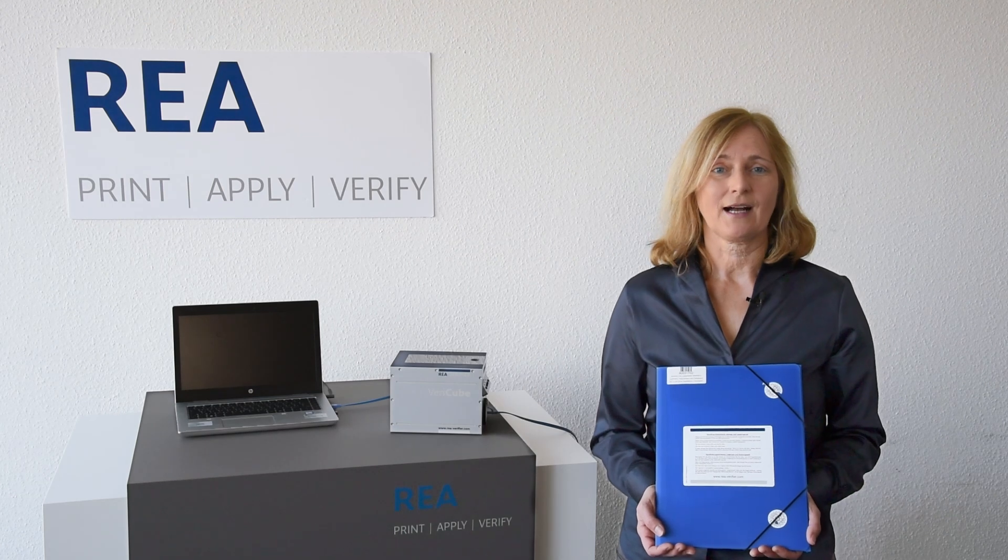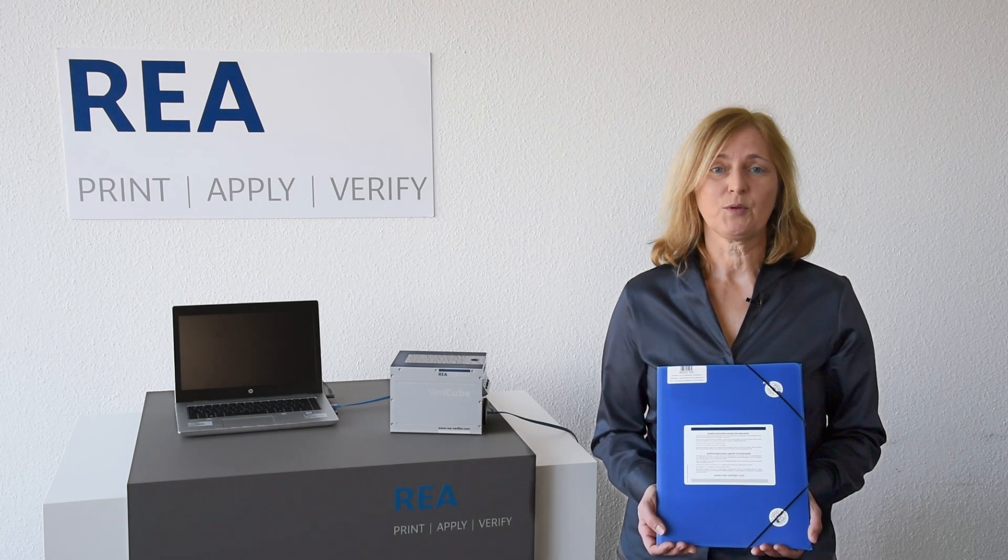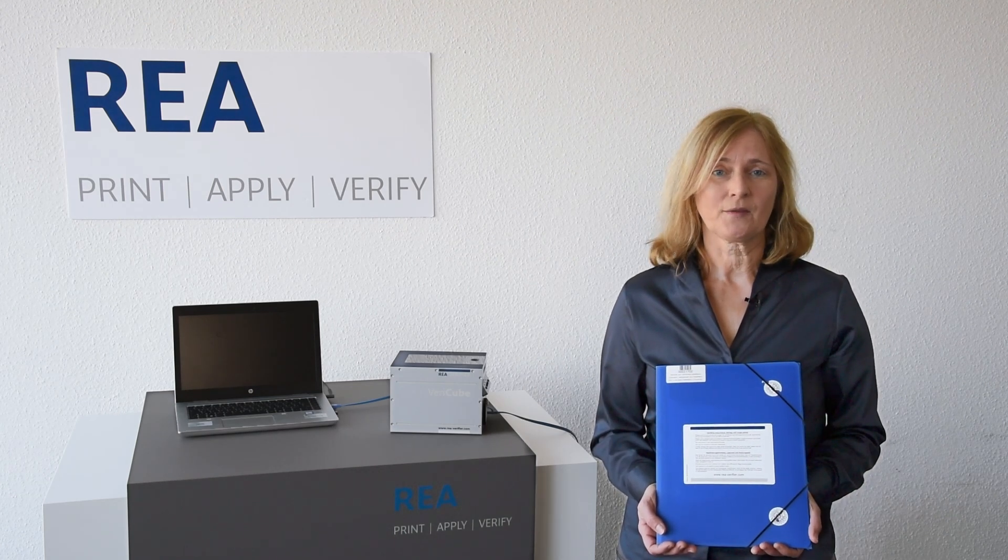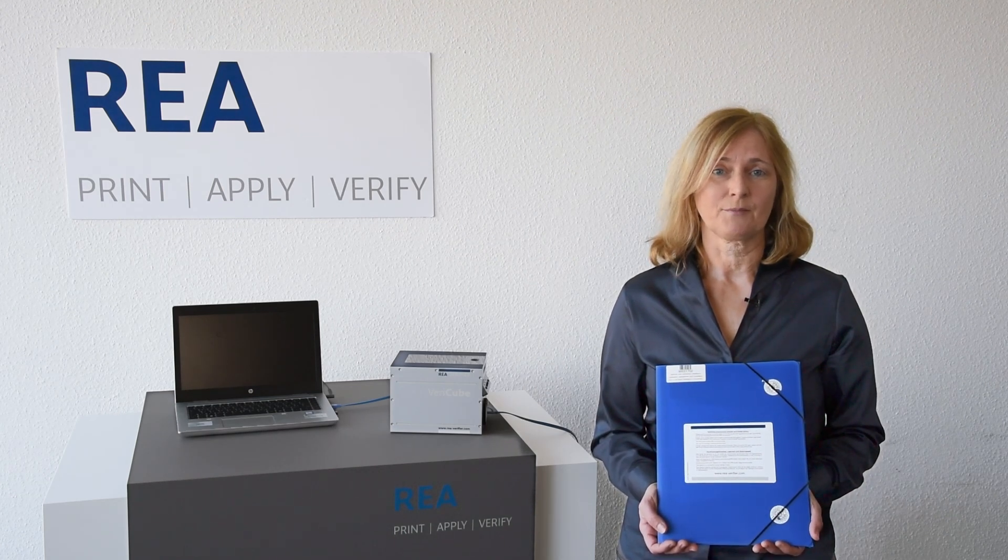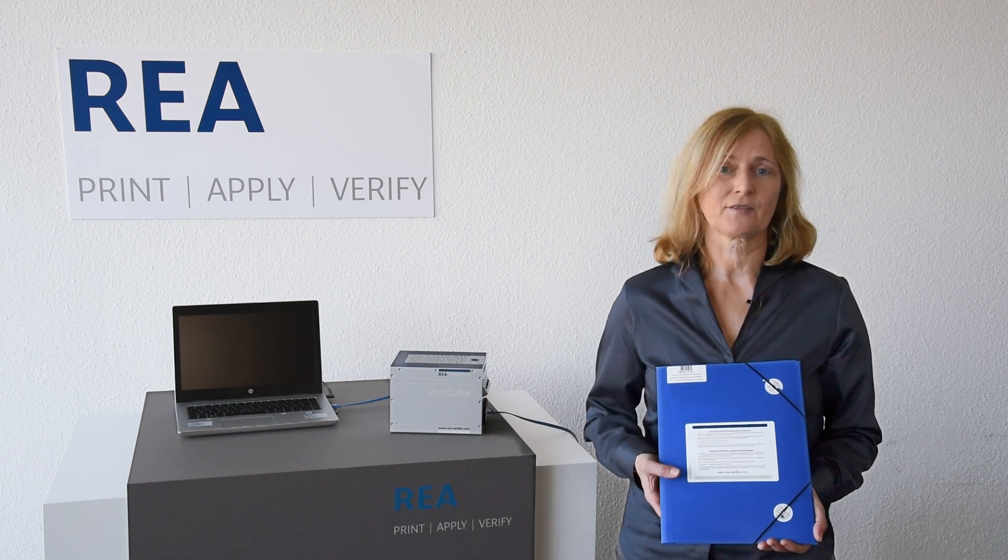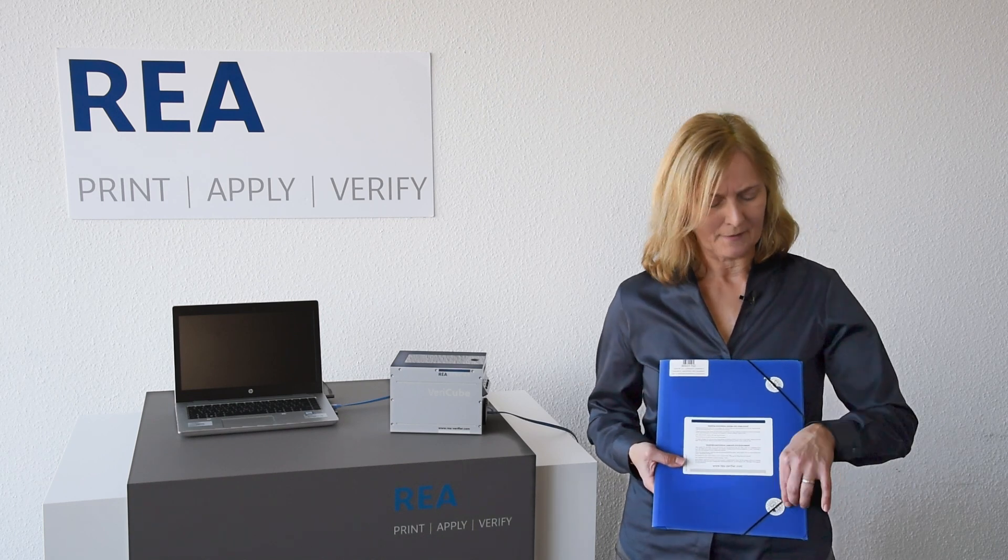The calibration cards are supplied in blue sealed folders. We open the folder with the calibration and adjustment card data matrix by breaking the seals.